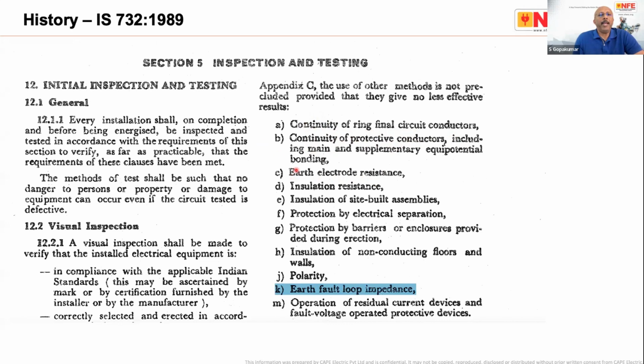Then 1989 has test number C, earth electrode resistance. After this edition of 1989, this test, earth electrode resistance, has been removed from the standard. So in the new standard, you cannot see this particular testing, earth electrode resistance testing, especially for low voltage systems, except at the point of commencement of supply under certain conditions.